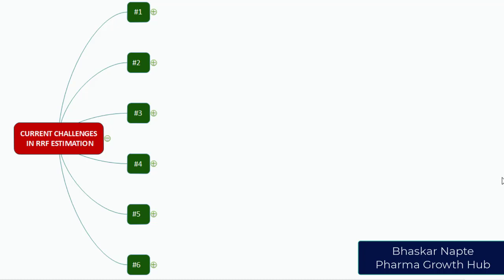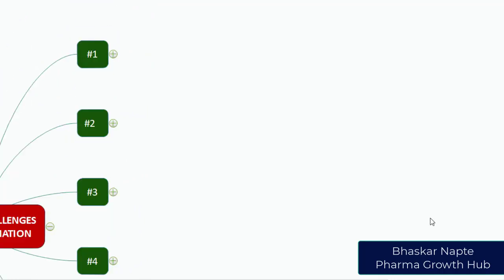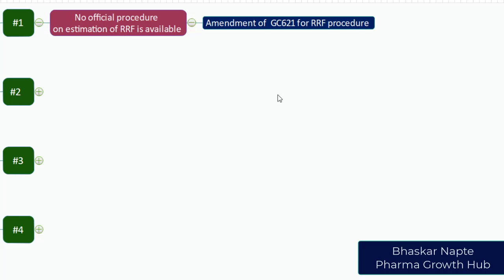These are the six challenges we are going to discuss. Challenge number one: no official procedure on estimation of RRF is available. Though we talk about the establishment of RRF, there is no officially declared procedure available for it. What is proposed is that the general chapter 621 on chromatography can be amended to include the relative response factor estimation procedure.